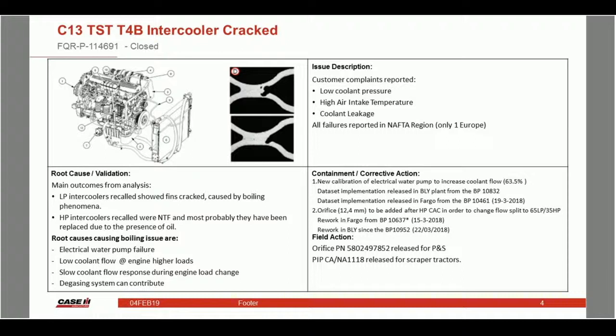So to optimize the flow rates, not only did we stop the pump returning to a lower flow rate at idle, but we actually changed the distribution of the flow between the two coolers. So there's now an orifice on the input to the high pressure charge cooler.